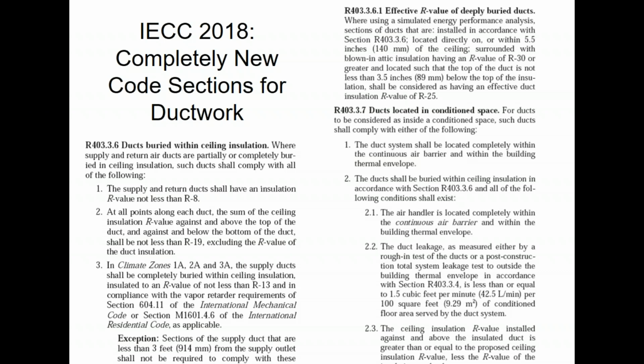So for you guys that are familiar with the 2015 code, this entire section did not previously exist. It's a little bit elaborate in how it's all worded, but essentially what it's saying is that the ductwork, if you put it under the insulation of the attic, it may or may not be inside the thermal envelope, because the thermal envelope is both insulation and air tightness related for the home itself. So you have to pay attention if you're going to try to not insulate attic ductwork and then claim that the attic insulation is in fact also the insulation for the ductwork.